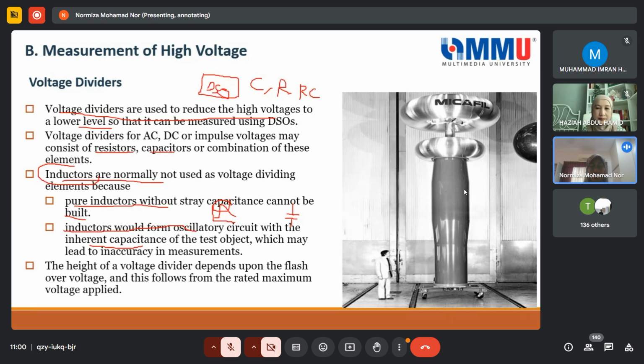consisting of the resistance, leakage impedance and the magnetizing branch, but in high voltage we only represent it as one capacitance here. So L with the C can give you oscillation, as I explained in the first few slides earlier. So this gives you inaccuracy. That's why inductors are not used as the voltage dividing element.